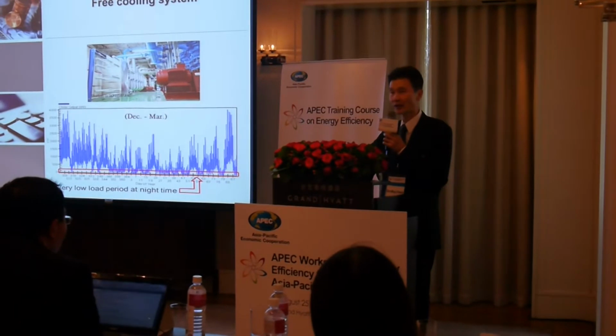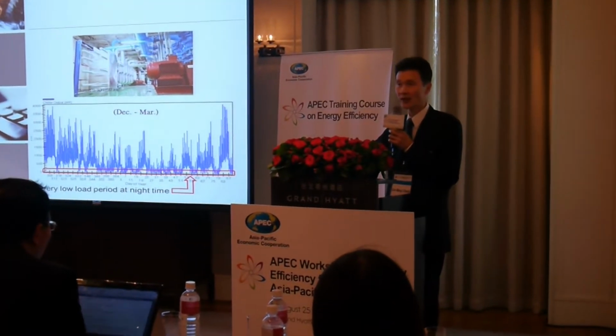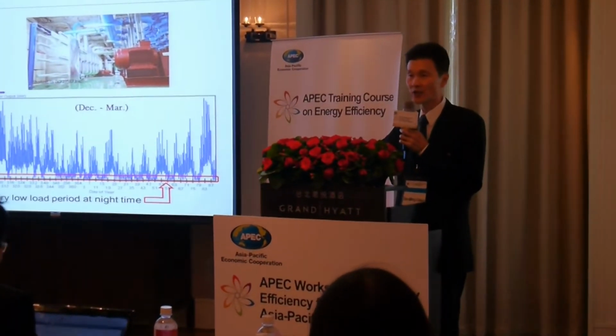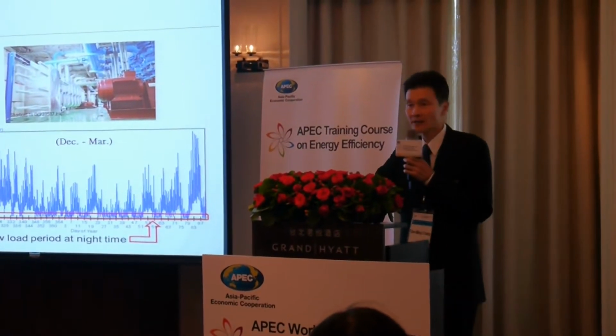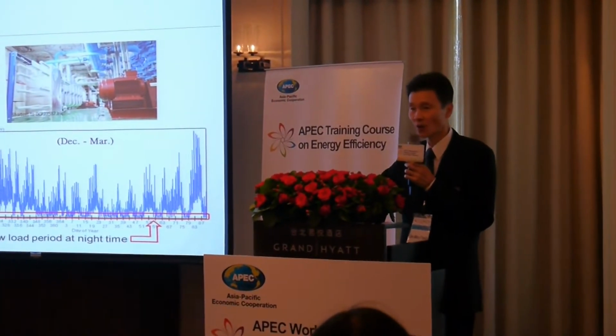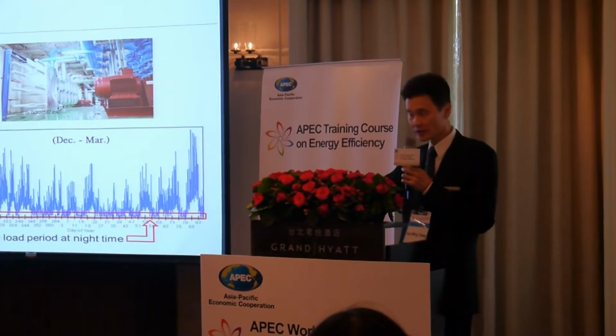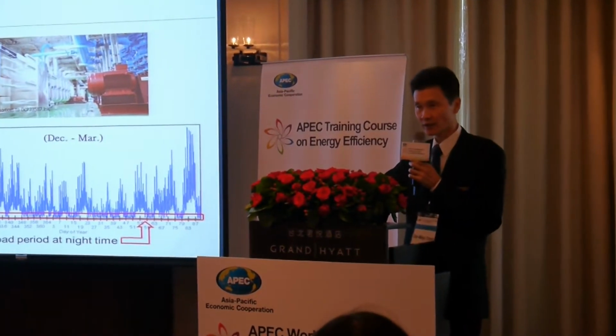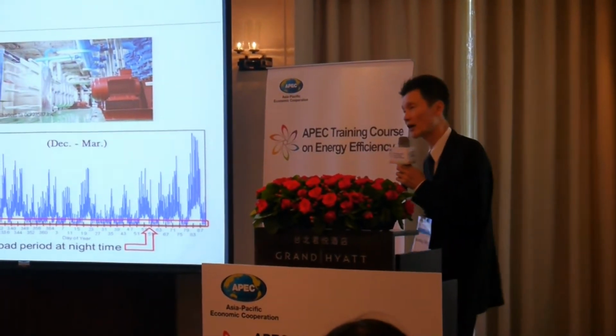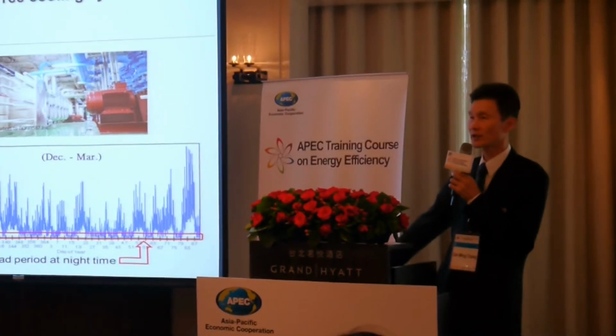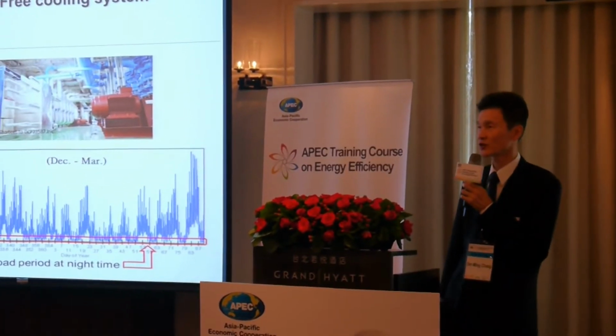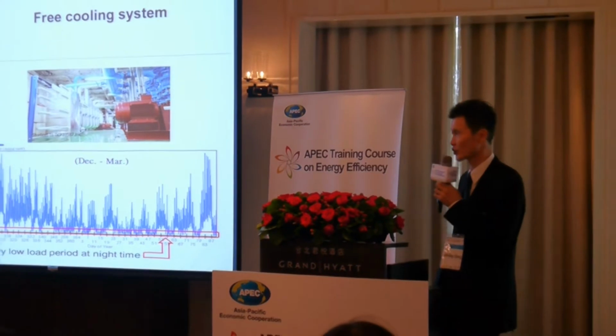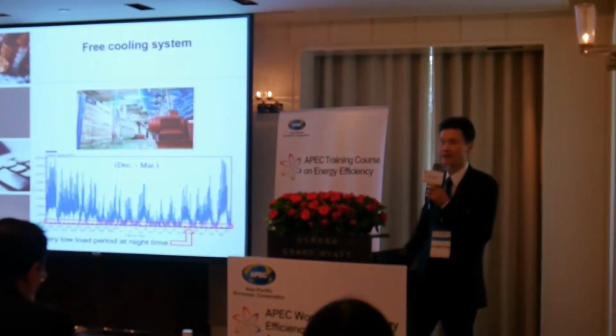Next, I want to introduce producing chilled water in North Asia, like Japan, Korea, Beijing, and Shanghai. In the winter time the outside is very cold, even snow, but the hotel is still using chilled water. So they just run the cooling tower, and this cooling tower water goes to the heat exchanger and transfers to the chilled water and supplies the system.